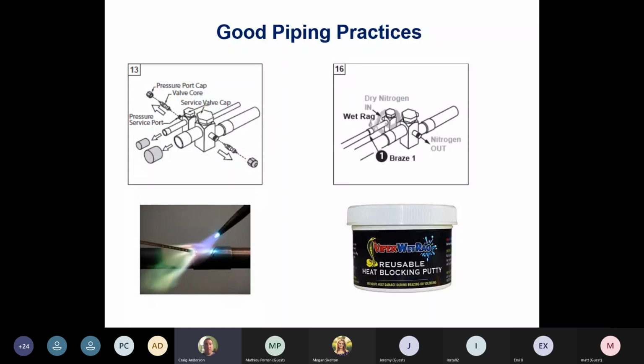If you overheat the service valve, you're going to have a hard time opening it. If you're using the ratchet wrench to open it, then this is where we're getting into stripping that valve. We've overheated it, and we're not using the proper Allen key to open it up. So get yourself some of this heat block putty. It's fantastic. Wet rags do work, but you'll notice that if you put a wet rag on there and we get some extreme heat, that rag is pretty hot after you're done. This stuff here keeps the heat from getting to that valve. Take the valve cores off, run dry nitrogen through. We're keeping the lines nice and clean, and we're drying them out as well when we're using the nitrogen. Just be mindful when we're doing those service valves.